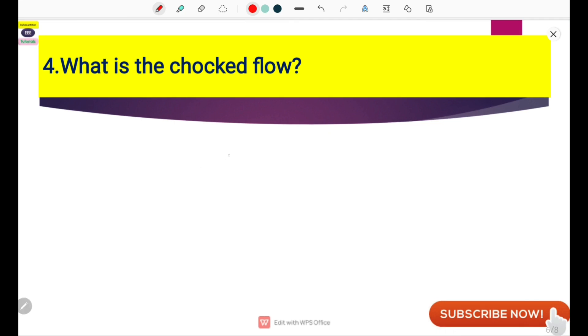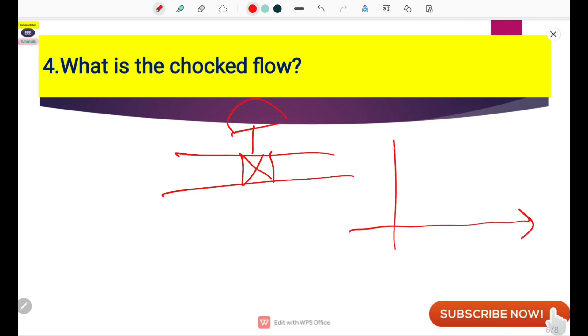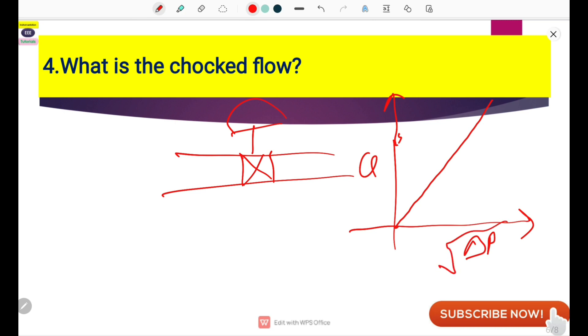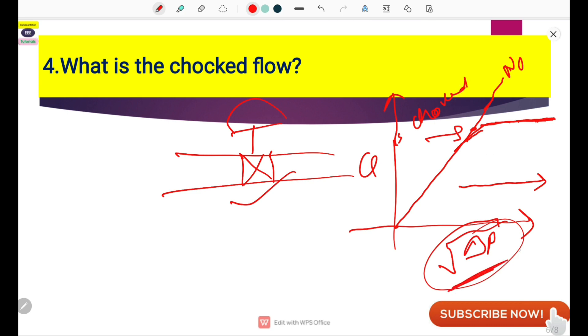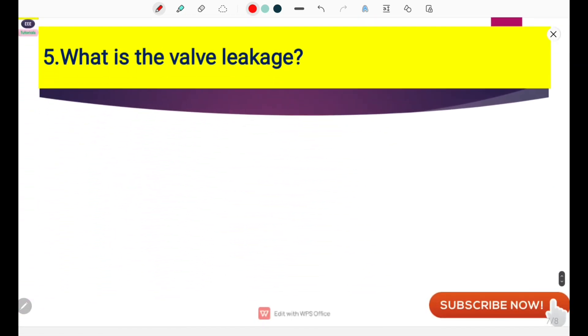Next is choked flow, which is also very important. We will understand this with the help of a graph showing flow on one axis and pressure drop (delta P) on the other. Generally, flow is directly proportional to the square root of delta P. Choked flow occurs when delta P is increasing but the flow remains substantially constant — it is no longer increasing. This is the definition of choked flow: flow does not change with respect to changing delta P.